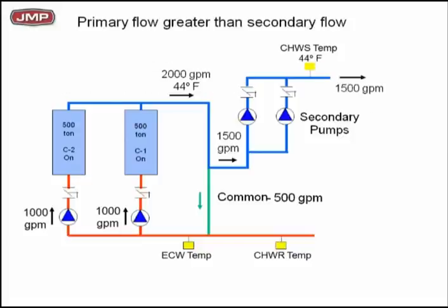So I take my 1,500 GPM of 44 degree water out to my system, and I bring it back 1,500 GPM at 56 degrees. And it's going to do what at the T? I'm going to have 1,500 GPM of chill water returned at 56 degrees, mixing with 500 GPM of 44 degree water to give me 2,000 GPM of 53 degree water returning. Now you see what you've learned. You see how important this is to get all this together.